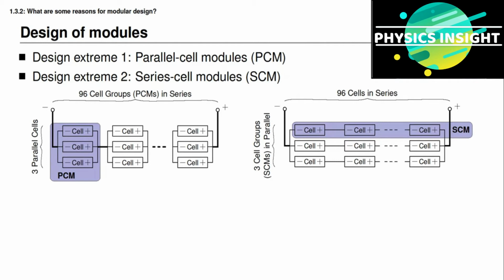There turn out to be some additional complexities to this second approach. We are required to measure the voltages of all cells, which is true in any case for lithium-ion battery management systems. But here, I need to measure all 3 times 96, or 288, cell voltages because they could potentially all be different, whereas in the PCM approach we were guaranteed each module of 3 cells had the same voltage by Kirchhoff's voltage law. In the second approach, they could all be different, so we must measure them all. Also, in the SCM approach, the individual cells will tend not to balance each other automatically, so there are additional requirements for balancing circuitry. So those are 2 disadvantages of the SCM approach.